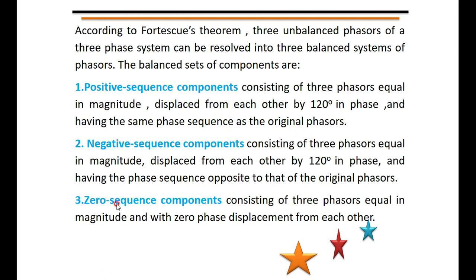The third component extracted from the unbalanced phasors is the zero sequence component. These are 3 phasors having equal magnitude, but the phase displacement between each other is zero — unlike the positive and negative sequence components which have 120 degrees of phase displacement. In the zero sequence component, all phasors have the same magnitude with zero phase displacement.